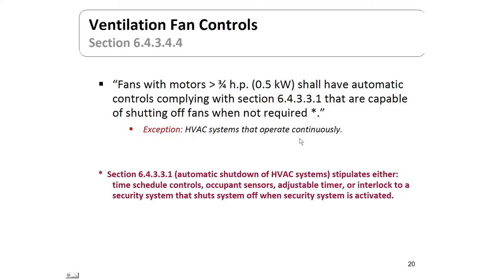Ventilation fan controls apply to fan motors greater than three-quarter horsepower. They need to have automatic controls complying with section 6.4.3.3.1, which stipulates automatic shutdown of HVAC systems via time-scheduled controls, occupant sensors, adjustable timers, or an interlock to the security system that shuts it off when the security system is activated. The exception is any HVAC system that operates continuously.